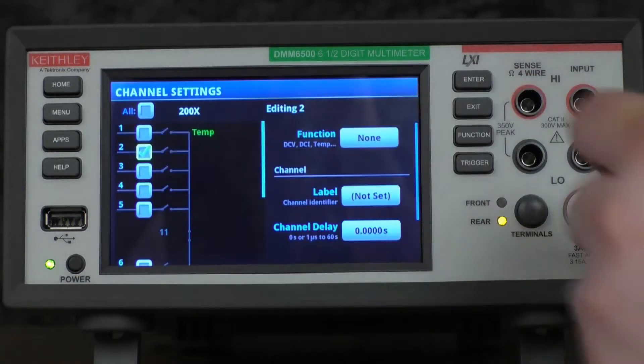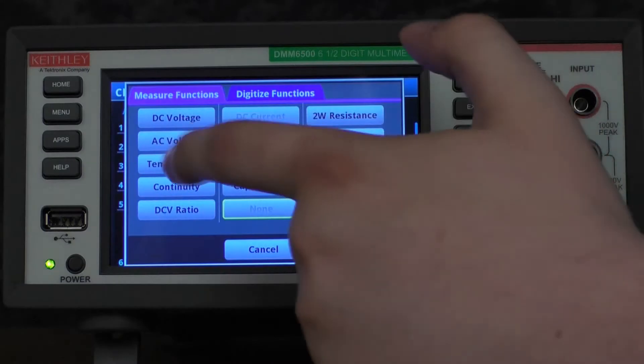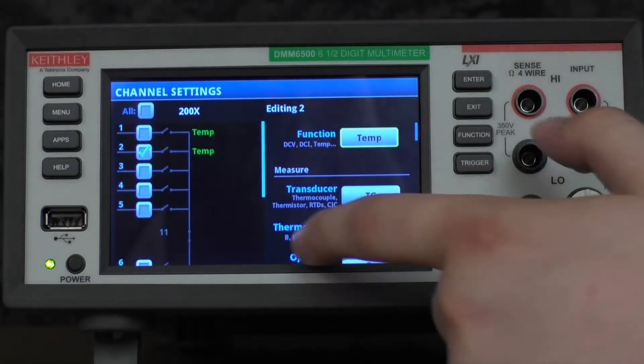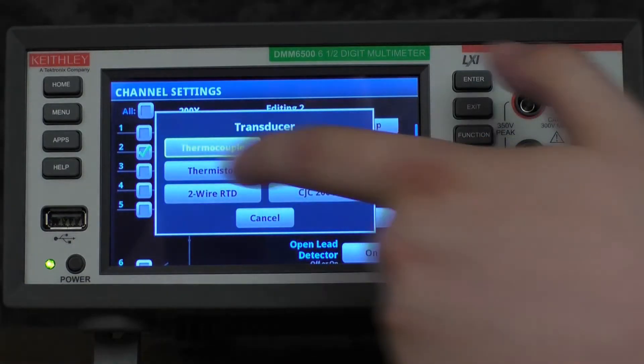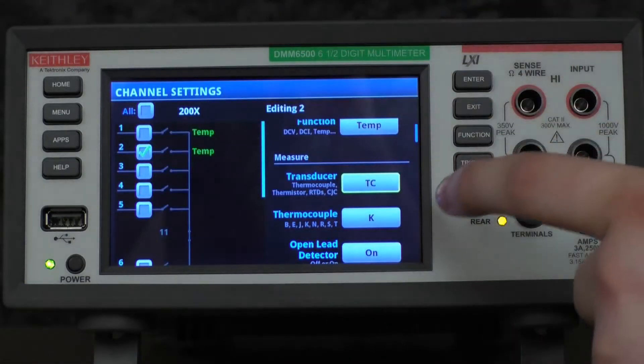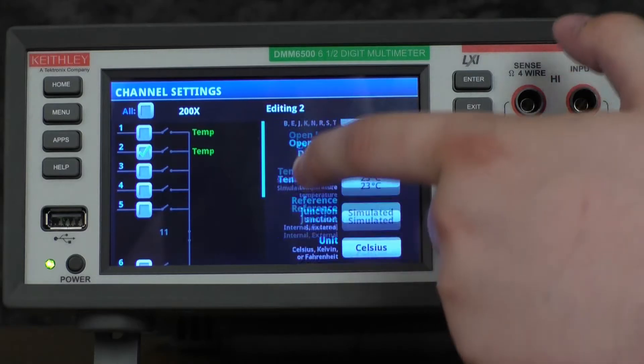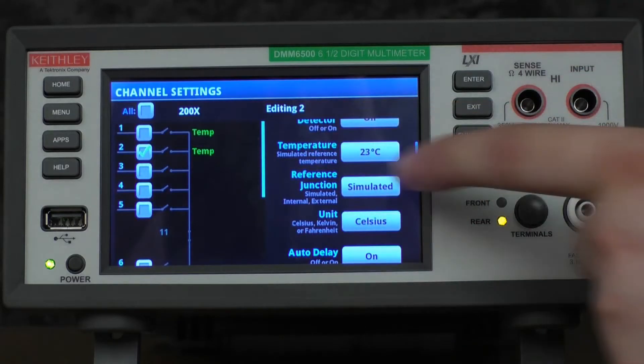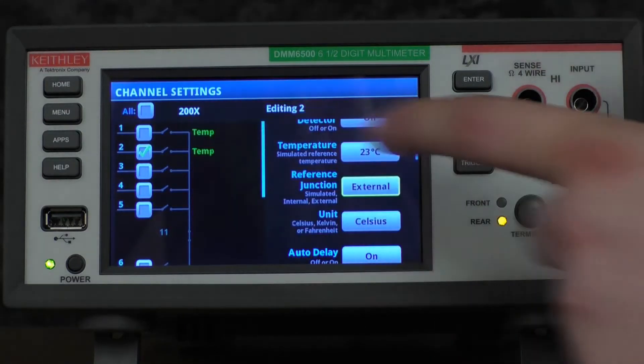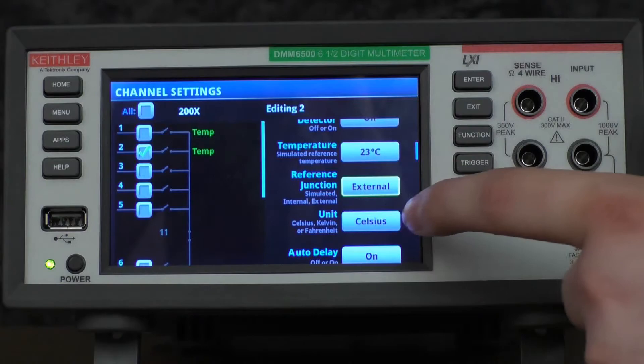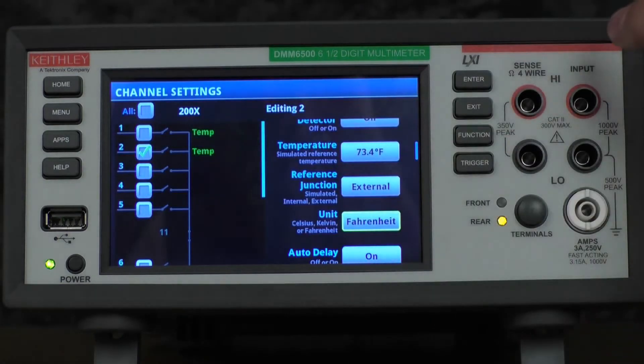We'll select channel 2, change our function to temperature, change our transducer to thermocouple type K. We'll then scroll down to the reference junction, change that to external, and change our unit to Fahrenheit.